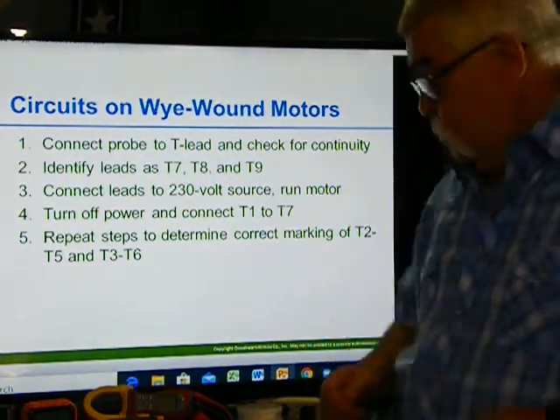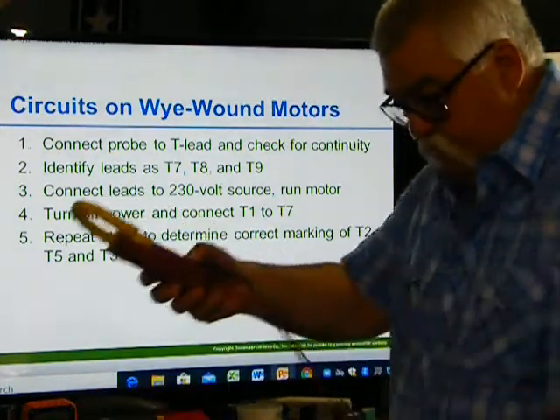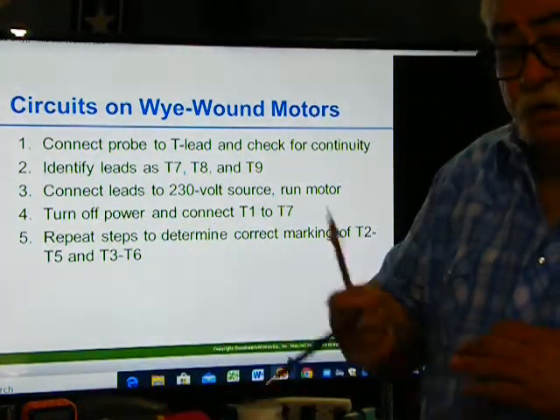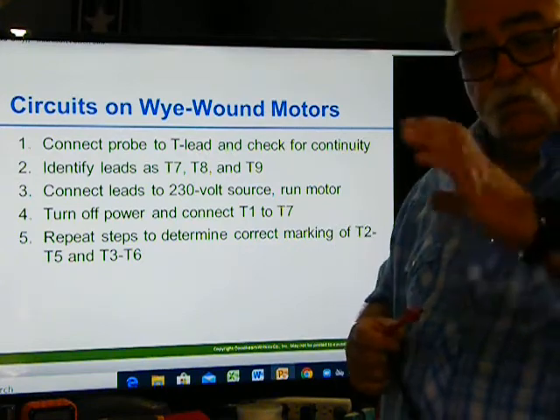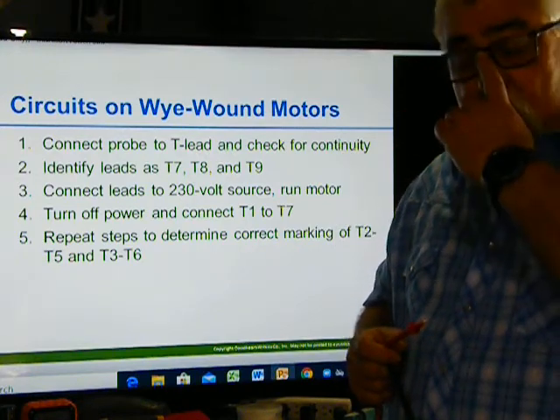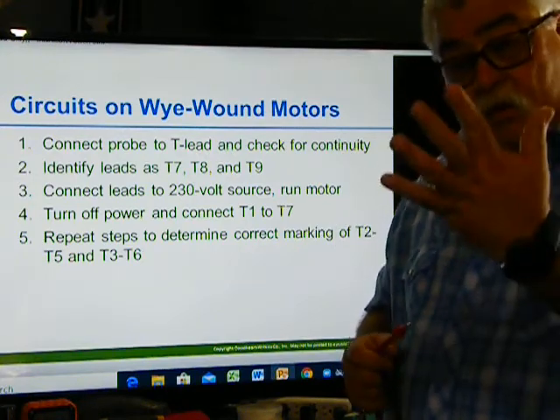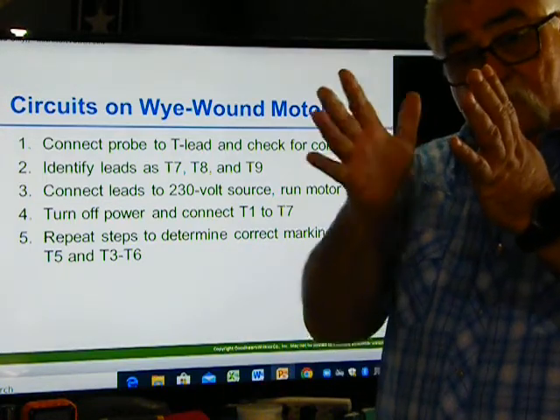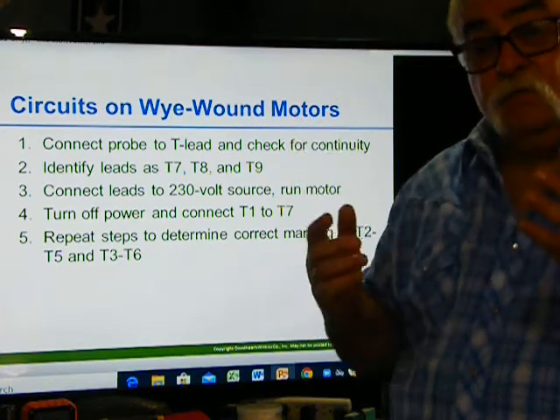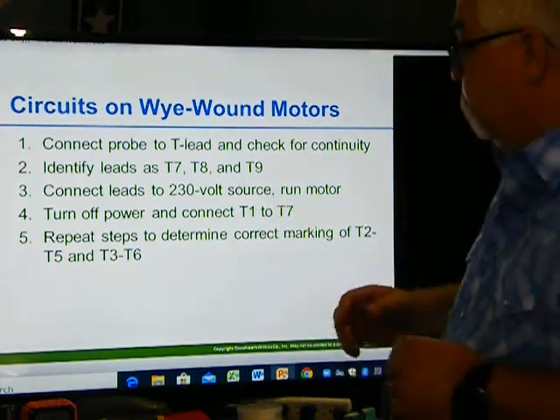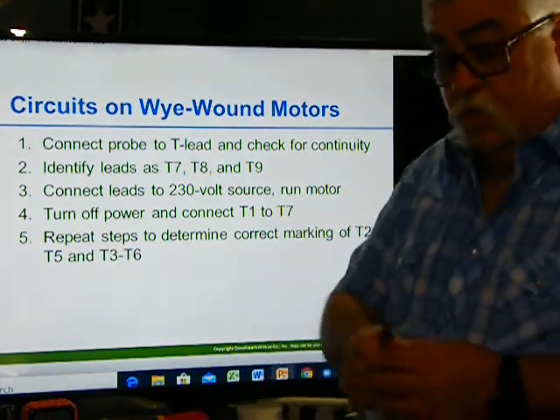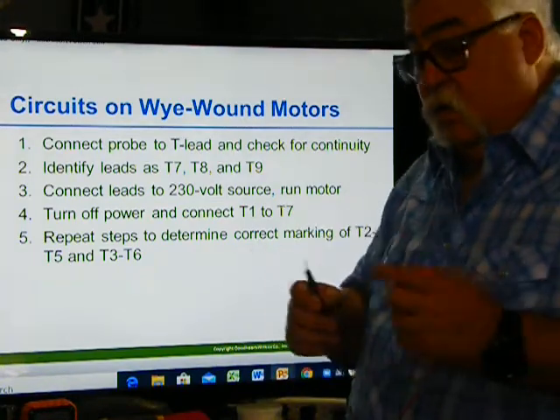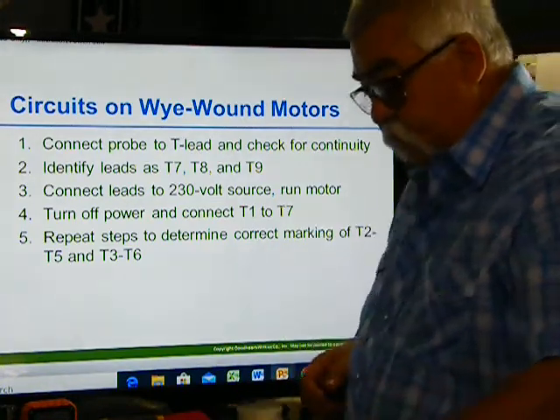Why? How can you do that? With your tester, you go to one lead. If there's no labels, we don't know. There's no nameplate on the motor, and all you've got is 9 leads sticking out. Well, you need to identify and find how you're going to hook up this motor if you don't know what your leads are. So when you touch one, you can go across the motor, okay?